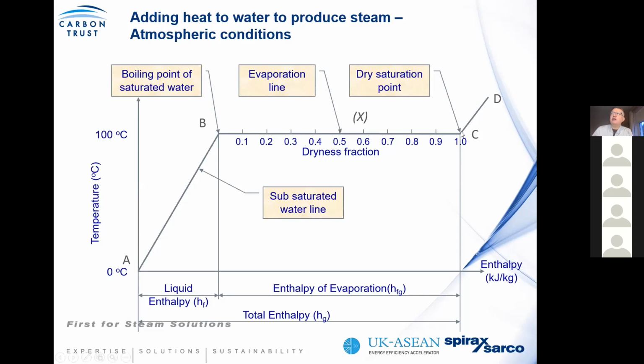If we add additional energy from point C to D, we go through the superheated phase, where basically we start increasing the temperature of the steam, and you would use superheated steam for the likes of steam turbines or certain critical plant. However, for most food and beverage industries, we only operate within the normal dry saturated steam region, because within the process, what we want is for steam to give up its energy at a constant temperature.